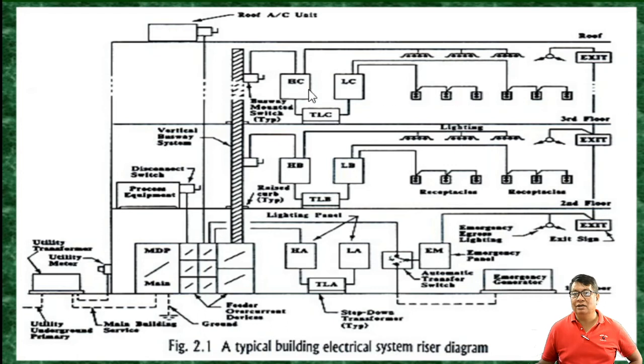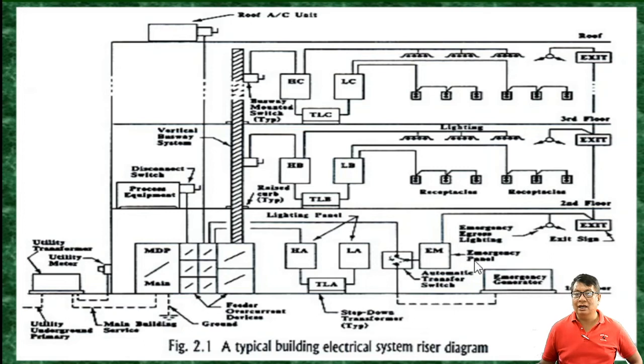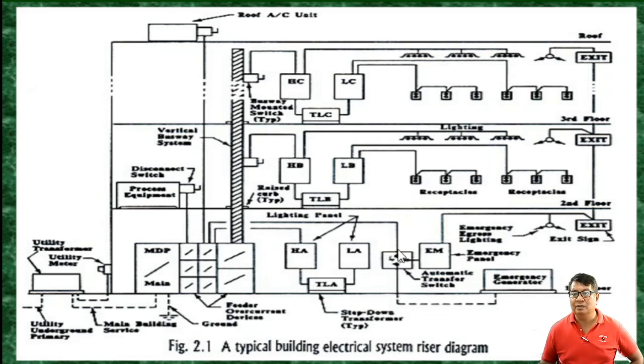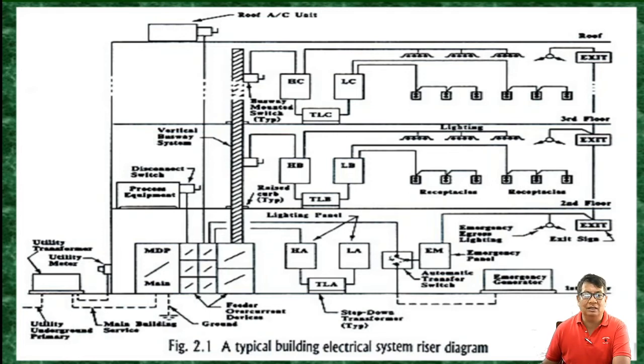In the riser diagram, the MDP is the main panel, with distribution feeders for each floor. There is a power supply going to auxiliaries. For each floor — first, second, third, and so on — panel boards are shown. On the first floor or basement, the emergency generator is located along with its panel boards and the automatic transfer switch (ATS). The ATS transfers power either from the generator or from the utility to the loads.